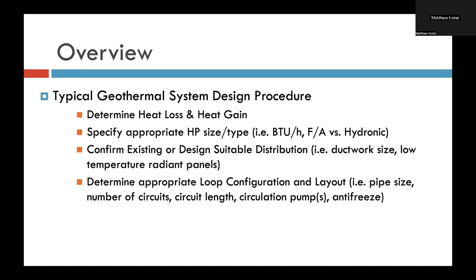And then, is the distribution system forced air or hydronic? And then you need to confirm the existing system in a retrofit application, or design a suitable distribution for this heat pump to rely on, whether that's ductwork size or, again, low temperature radiant panels. And then once you've specified the heat pump and the distribution system, you need to determine the appropriate loop configuration and layout, that is pipe size, number of circuits, circuit length, circulation pumps, and antifreeze. Next.